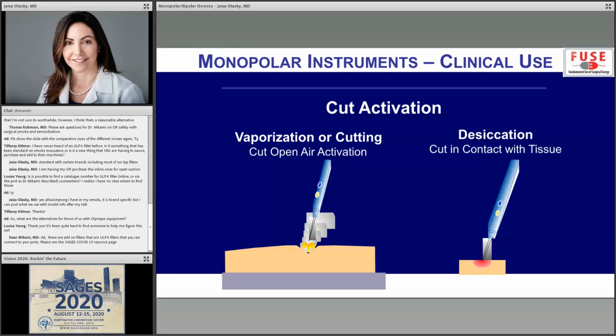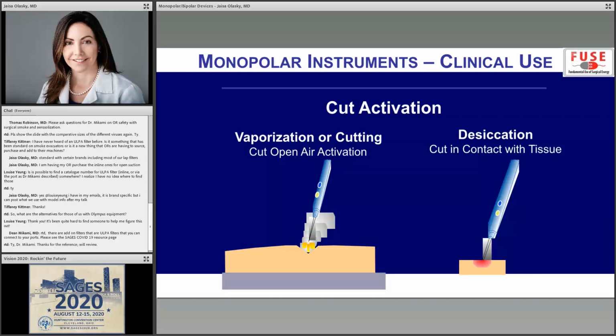But essentially, if you're trying to make that perfect vaporization pocket, which is what's going to almost mimic using a scalpel and giving you a nice incision, if you like to use your energy device on skin, you would want to do that. That's going to be a near contact mode where you're not quite touching the tissue. That is different than open air activation where you're just like waving the pencil around in the air. That's dangerous. Using a near contact mode is going to give you that desired tissue effect.